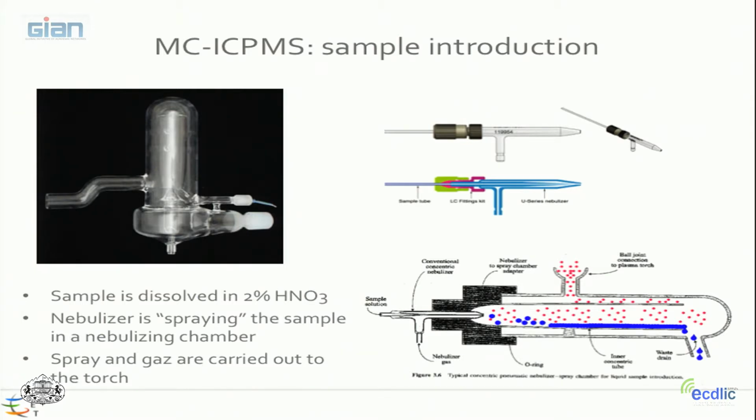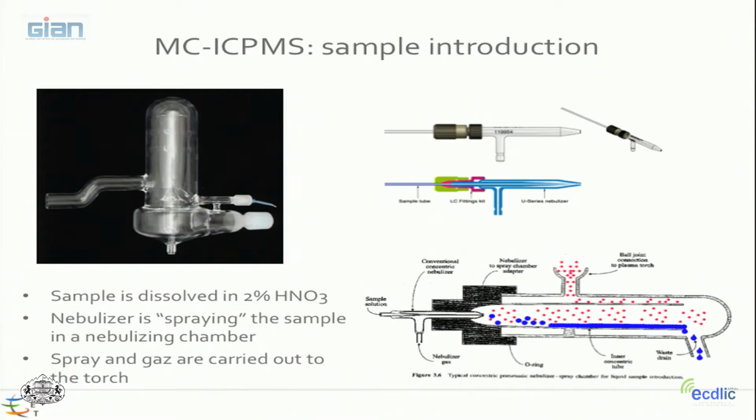using a capillary tube here, we suck out the solution and we introduce it into a spray chamber to transform this water, or slightly acidic water, into very, very tiny droplets, so that they can burn in the plasma. We need to spray, like an air spray. The gas which is used to spray is argon, because argon is the main gas used in ICP-MS. This is a typical spray chamber. So you have an injector. This is the spray of your air spray. Okay. Here your sample is coming.